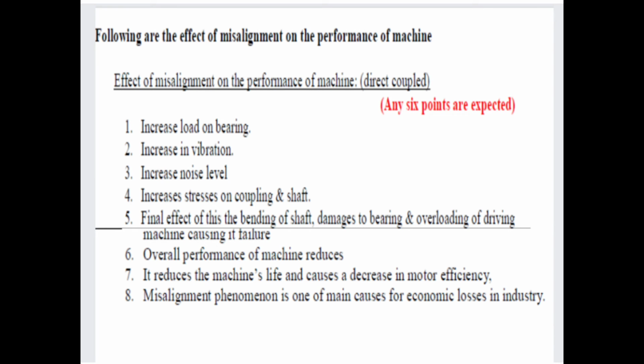So the following are the effects of misalignment on the performance of a machine, in a direct coupling. First is increased load on bearing. Second is increase in vibration. Third is increased noise level. Fourth is increased stress on coupling and shaft.